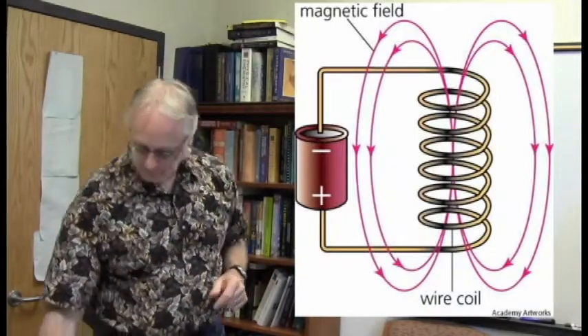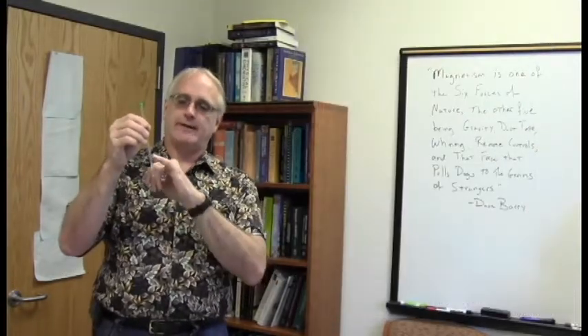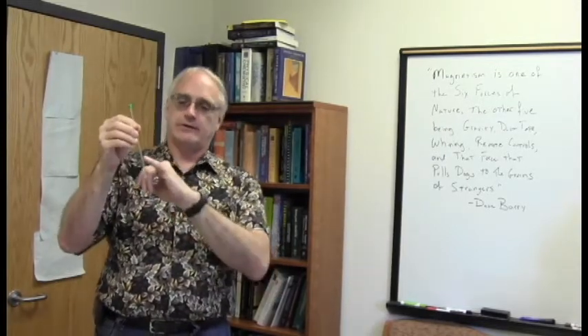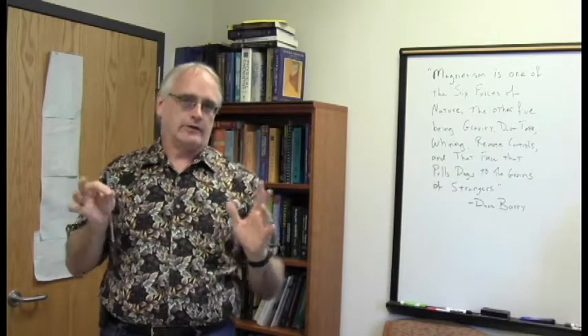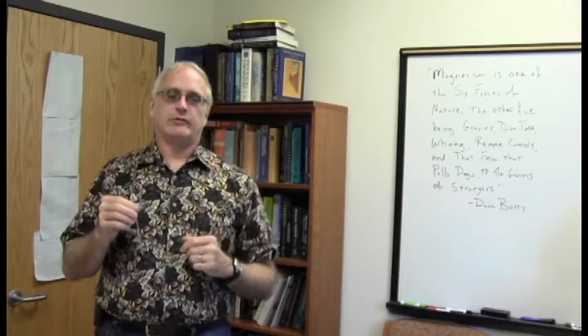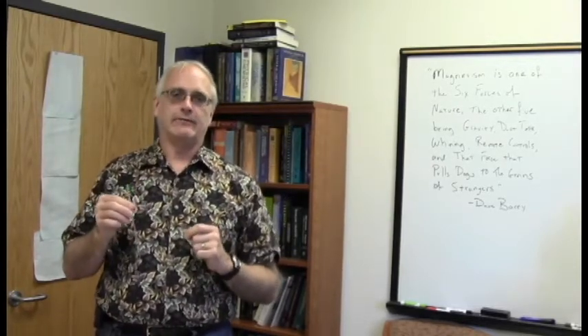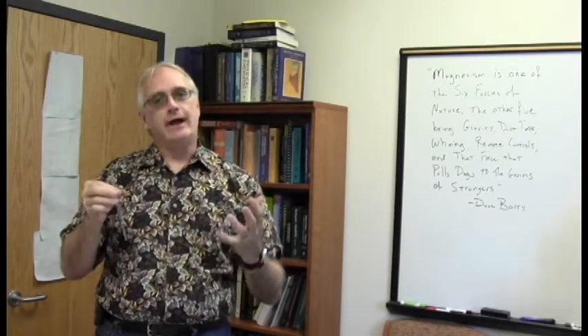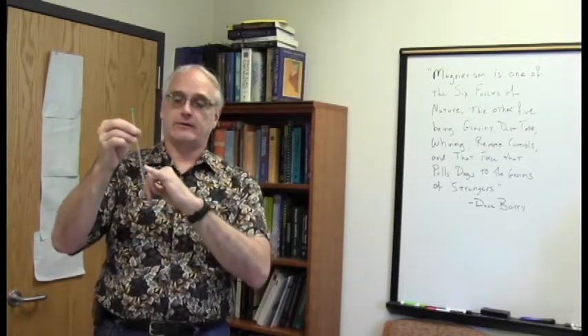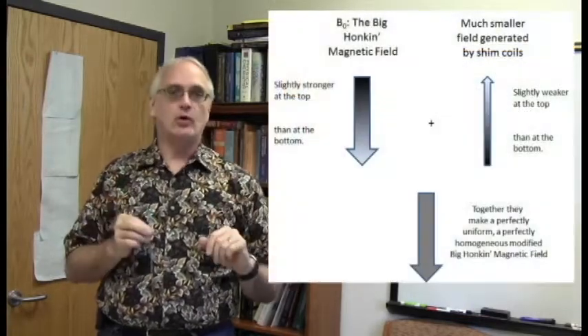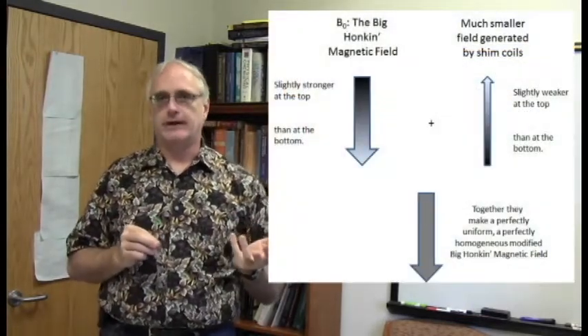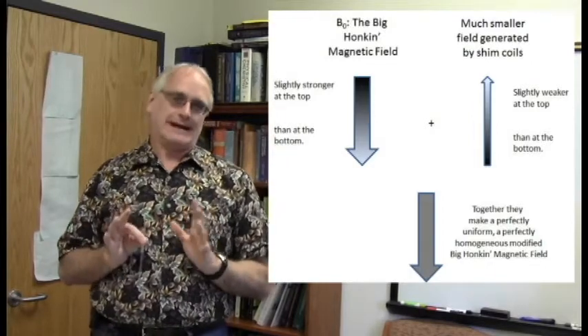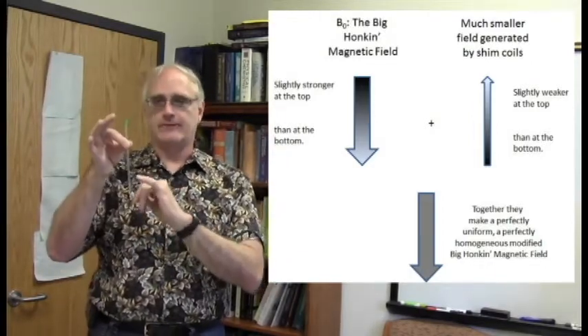For example, if the magnetic field felt by the top of the tube and the bottom is slightly different — meaning protons there change their spin state differently — the shim coils generate a slight modifying magnetic field. Let's say the main field is slightly stronger at the top, so we control the current through a shim coil to generate a field slightly stronger at the bottom. If we work it right, those two perfectly balance each other and create a uniform magnetic field throughout the tube.